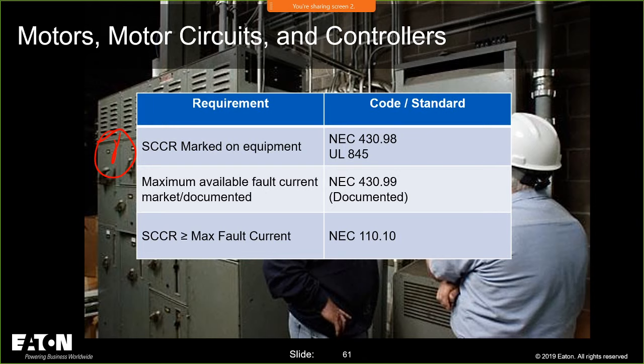The second part of that recipe is to know your fault current, and that's required to be documented, not field marked, documented as part of 430.99. I believe I said field marked earlier. It's not. This is a case of documentation only. And then you have the third line item, NEC 110.10, which tells you they have to be compared.